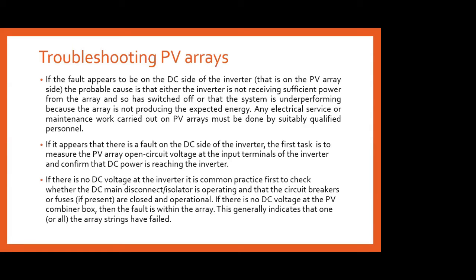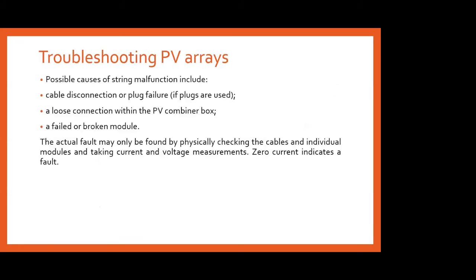And when there is a problem with the array, then one or the other array may have failed. So we first check your ACs, then we check your DC part. To check your DC part, of course, we have to check your DC isolators, the connectors, the fuses, and everything by measuring the output voltage and all those things. Then if there is no problem with your DC part, that is your isolators or disconnectors, the fuses and all those things, then we have to check the combiner boxes. If there is no fault with the combiner boxes, then the problem will be with respect to my arrays itself. That is, one or the other array may have failed.